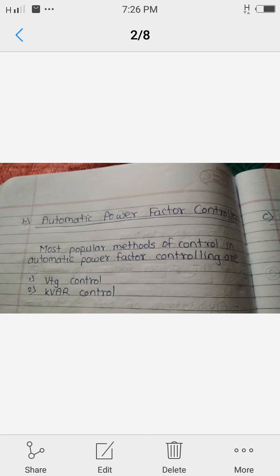Most popular methods of control in automatic power factor controlling are voltage control and kVAR control. kVAR sensitive controls are recommended where voltage level is closely regulated and not possible to use as a control variable. Now see the voltage control.